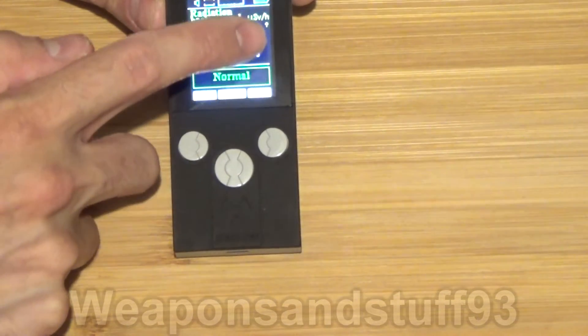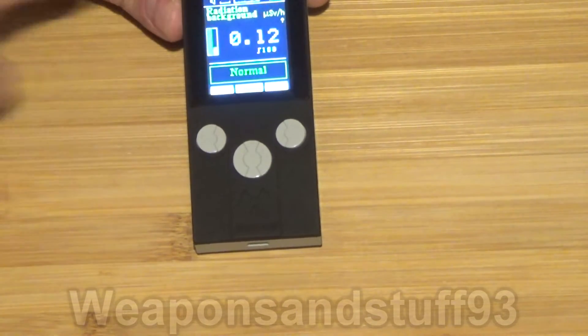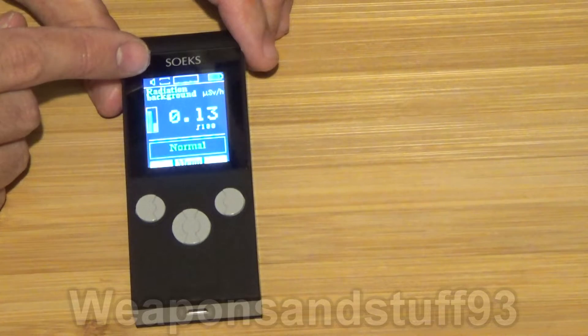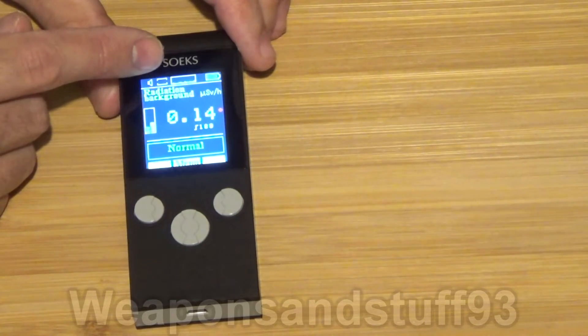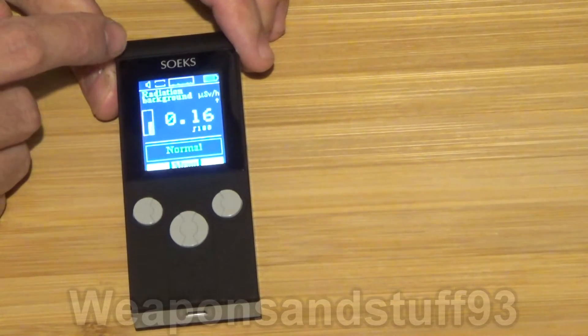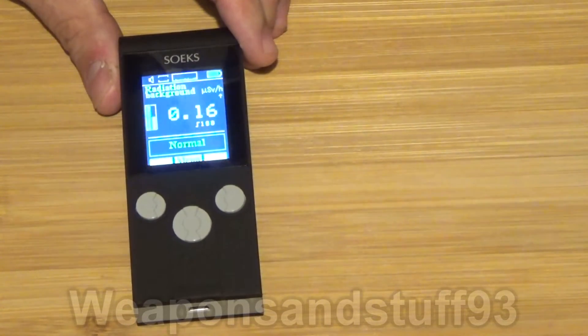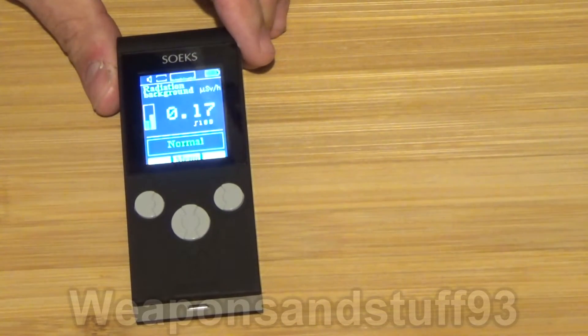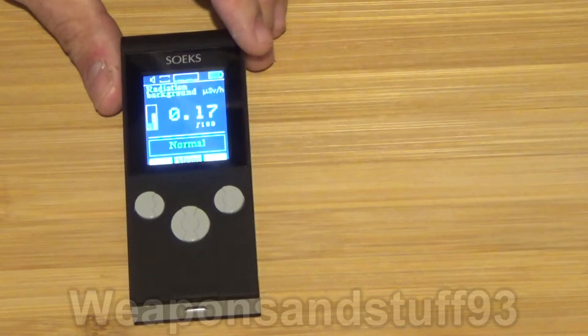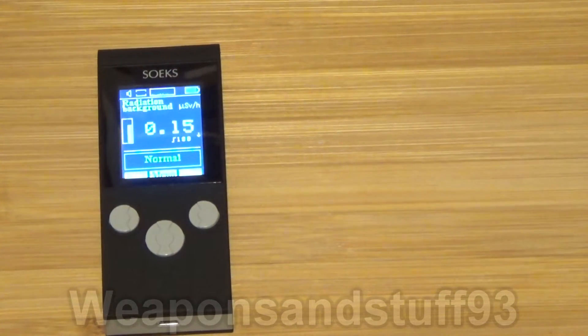What you can see here is it's constantly scanning for radiation. That's the current dose there, with a little arrow showing it going up. Where it says µSv/h, that's micro-sieverts I believe — that's background radiation. There's a little speaker symbol showing the sound is on. The empty brackets show your total accumulated dose; as that fills toward the end it goes from green to red, and when it hits red it's saying you should get out. You set the alarm threshold in the settings. The graph shows current radiation for the last 30 seconds or so, and at the end is the battery symbol. Where it says 'normal,' that means we're currently exposed to a normal amount of background radiation.